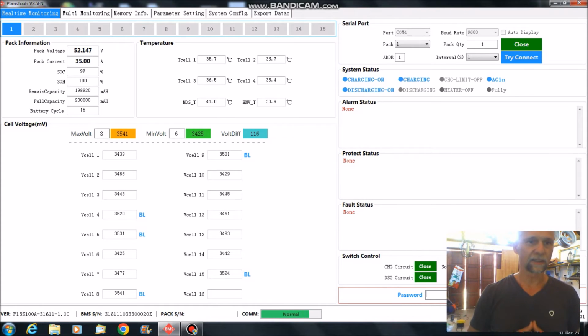So it's 99% state of charge, just a tiny bit left until the BMS will hit the cell over voltage at the first cell. You can already see cell number 8 is almost at 3.6, it just took a few seconds. Now the alarm is there.